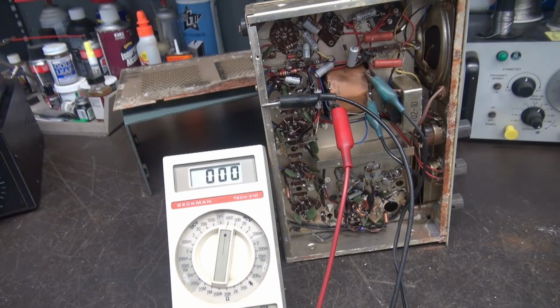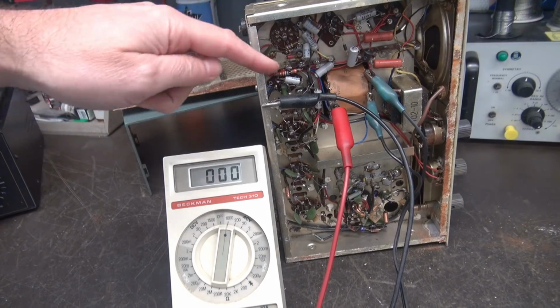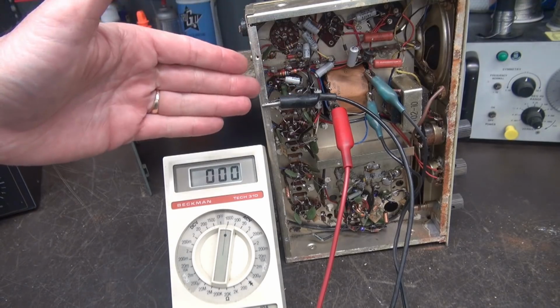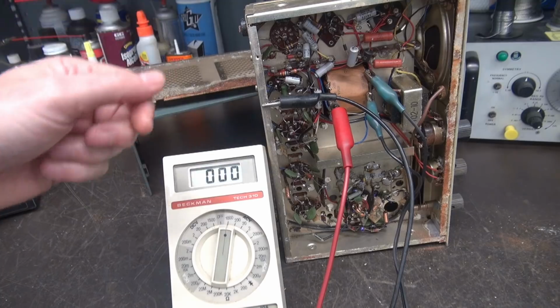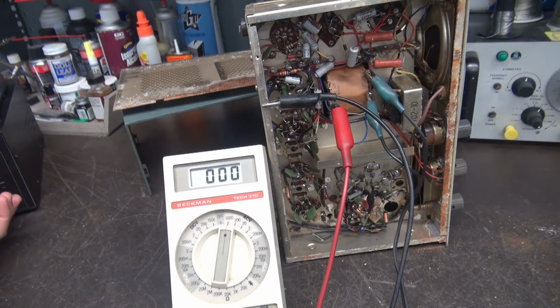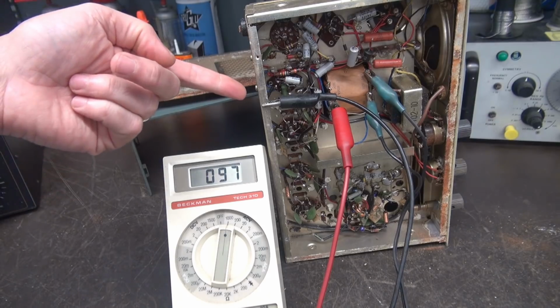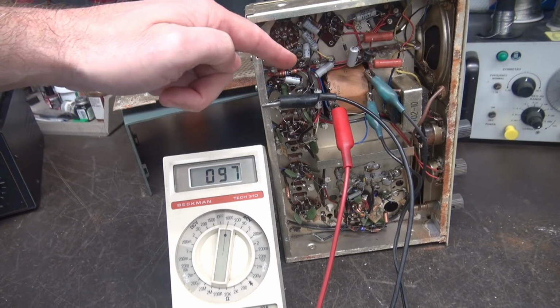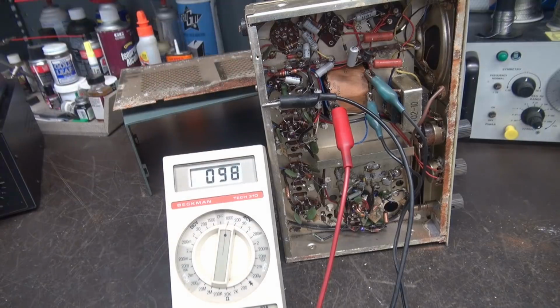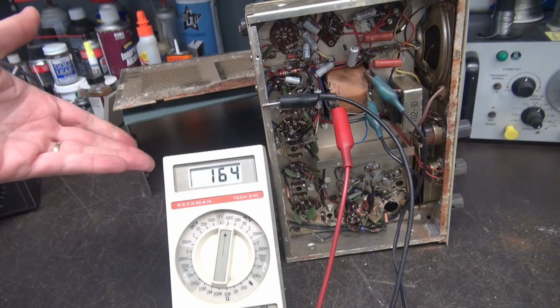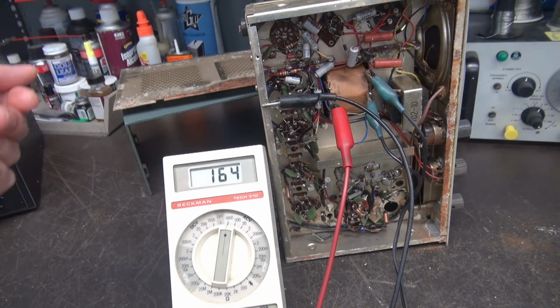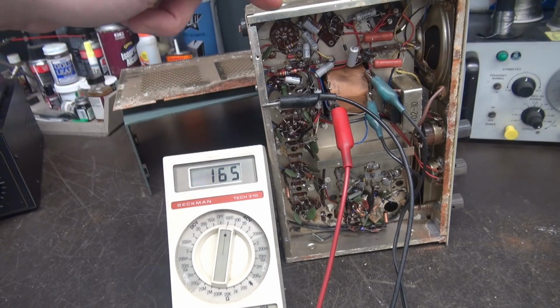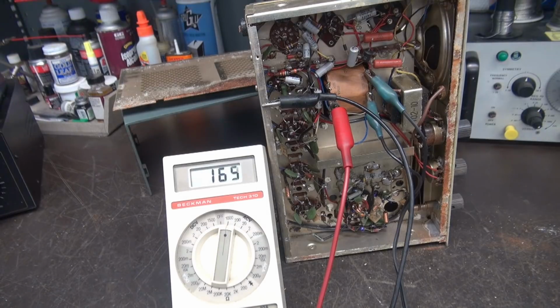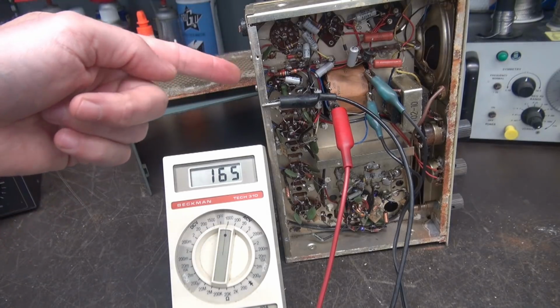Back to the question, did the high voltage side, the 160, actually have a center tap lead on it? The answer is yes. I'm bringing up my variac again. In this case, my meter, one side is hooked to chassis, one side is hooked to one of the 160 volt taps. So if you look, there's about 120 input, and got about 160 something volts.